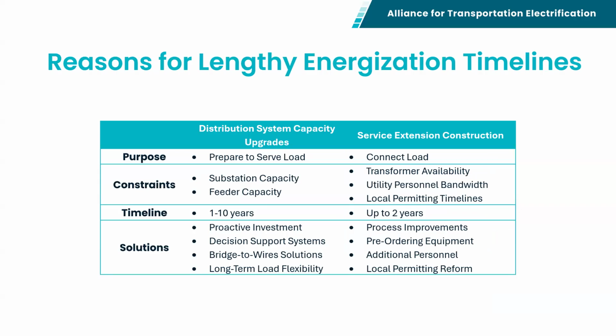In this paper I wanted to break down these two distinct reasons for a lengthy energization timeline. A distribution system capacity constraint requiring upgrades is really about the utility preparing to serve that load. A service extension construction is just connecting the load to the grid, whereas distribution system upgrades are about making sure the grid can actually serve that site. The constraints look like substation capacity or feeder capacity, versus permitting or transformer availability, which falls more into the service extension bucket. The timelines are really different here.